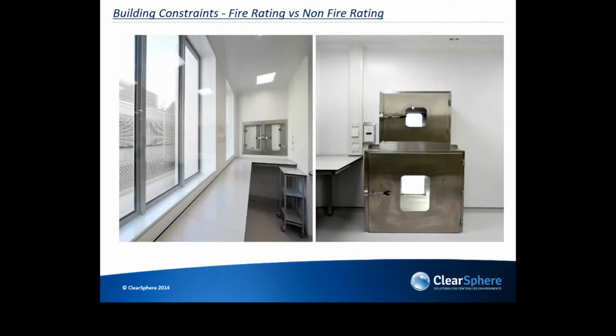So we spoke about fire constraints. On Vincent's Hospital, we have a storeroom as part of the facility, and that storeroom had a fire-rated envelope. What you'll see on the left-hand side is one of the lobbies where you transfer materials from outside through the pass-through hatch to the facility, and vice versa. That pass-through hatch was installed in a standard wall, so it's a non-fire-rated pass-through hatch. Whereas the photograph on the right-hand side is within the compounding storeroom, and that is within a fire-rated envelope. So the same pass-through hatch obviously needs to be a lot bigger, a lot more involved in the engineering of it. That's a fire-rated pass-through hatch for getting materials in and out of the store.